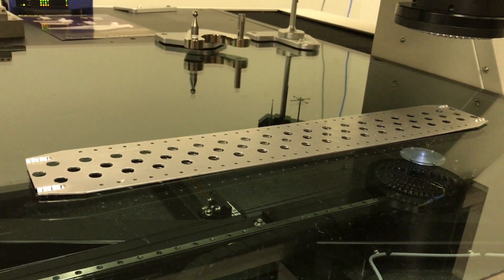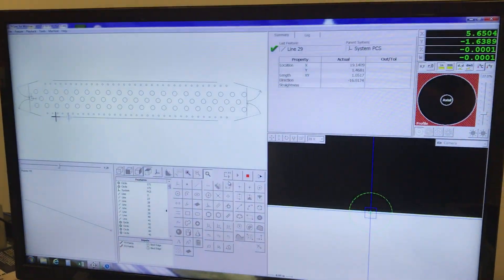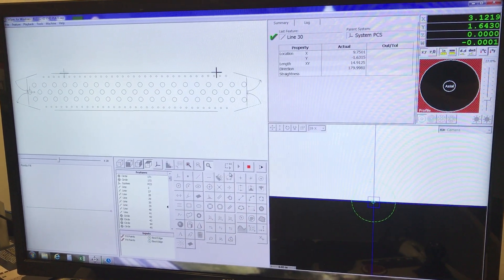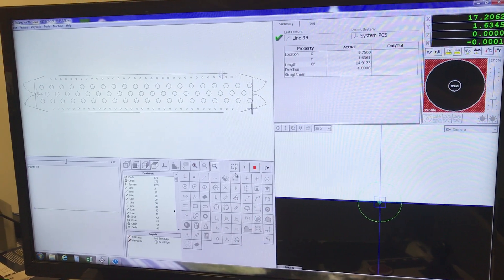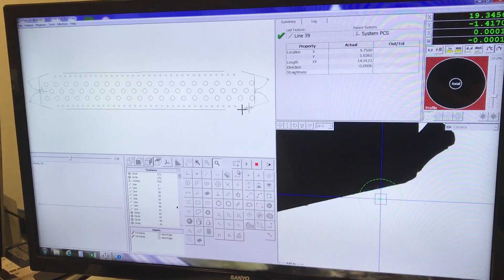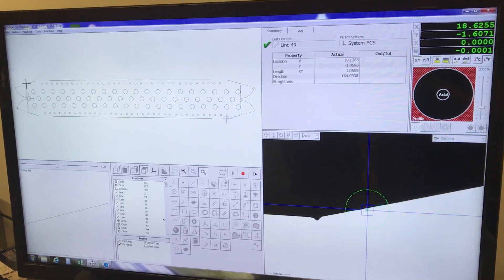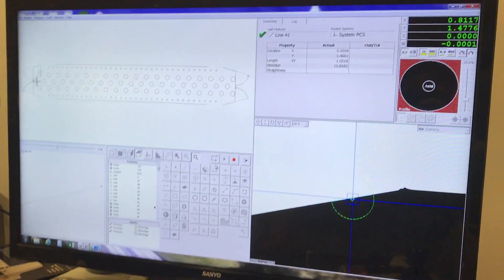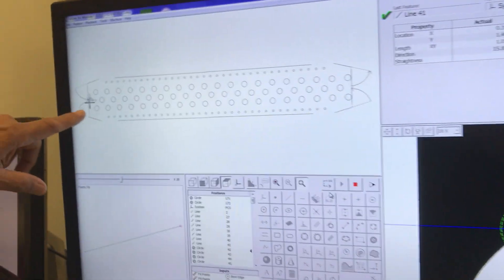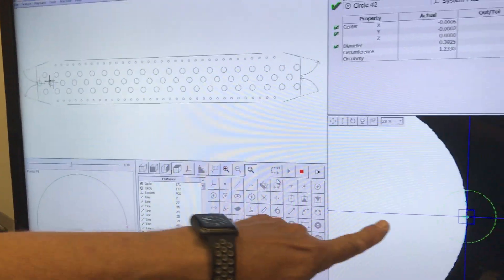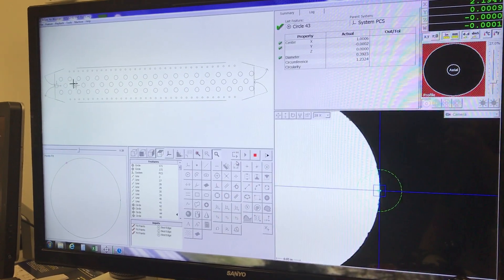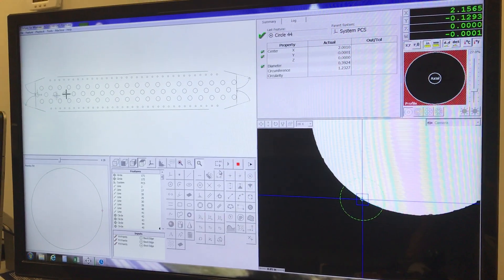After we measure all the angles, we're going to come over and measure all the holes. You'll see it measuring the diameter of each one of the holes. We're doing it with three points — we could have done it with more points if needed, but three works really well.